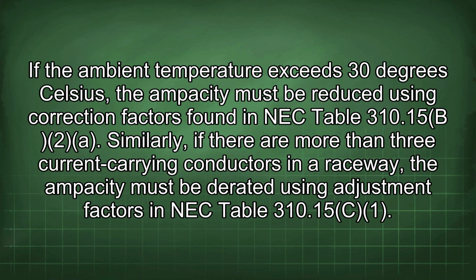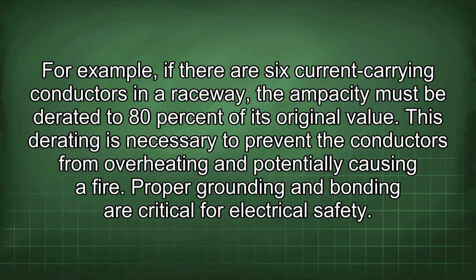If the ambient temperature exceeds 30 degrees Celsius, the ampacity must be reduced using correction factors found in NEC Table 310.15(B)(2). Similarly, if there are more than 3 current-carrying conductors in a raceway, the ampacity must be derated using adjustment factors in NEC Table 310.15(C)(1). For example, if there are 6 current-carrying conductors in a raceway, the ampacity must be derated to 80% of its original value. This derating is necessary to prevent the conductors from overheating and potentially causing a fire.